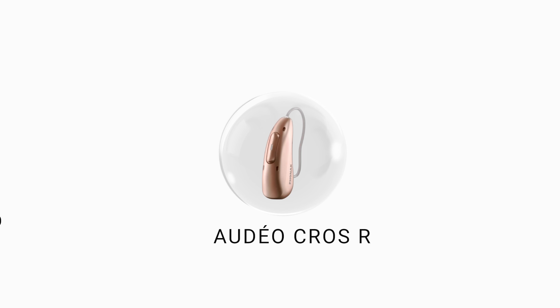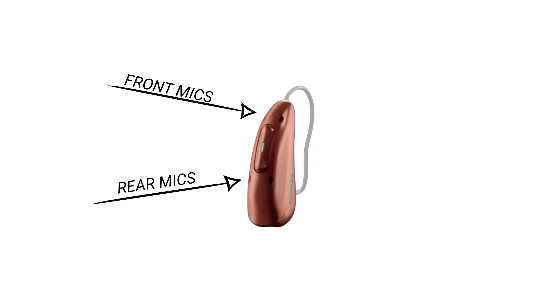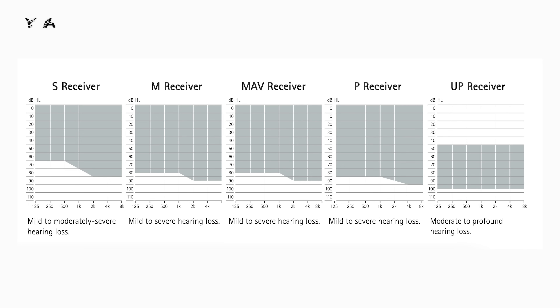Phonak's attention with the new CROS system has been on battery life, with a 30% improvement, overcoming all the issues they've had with previous CROS and BiCROS systems — a weakness they'd be the first to admit. Taking you on a physical tour, they look pretty similar to Phonak's previous model, the Audeo Lumity, specifically the Lumity Life, though they are a little bit shorter. The microphones have dual ports for both front and rear-facing microphones, and there's been a slight modification to the rocker switch, sitting a little lower. This rocker switch can be used for changing programs, volume and answering phone calls. I'm particularly happy Phonak have stuck with two buttons, as all other manufacturers seem to be going towards a single button option. You'll also see the receiver wire, which feeds energy and information to the speaker sitting inside your ear.